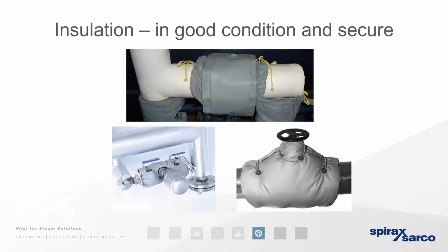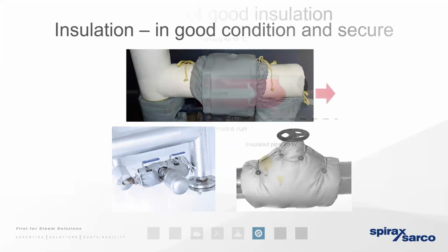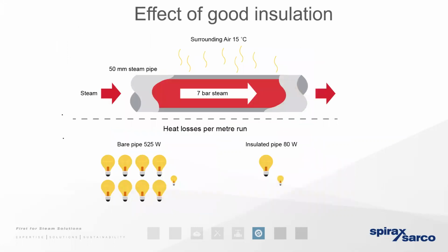So we've also mentioned insulation, and that can have a huge impact on condensate load. That's because of the mass of metal that's involved with any flanges, strainers, separators, trap sets, valves, and any other ancillaries. We need to ensure that we've got the best possible grade of insulation to protect that mass of metal, because that's where we expect a significant amount of heat loss to take place. So again, we've got calculators and configurators that can help you understand the importance of ensuring that we keep that grade of insulation as high as possible.